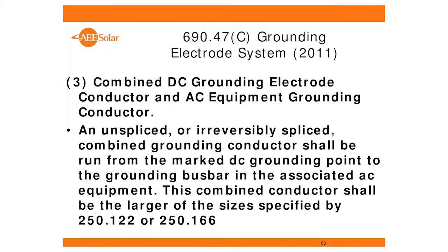Okay, so the common AC and DC grounding electrode is where I take our DC to ground here and our AC to ground there. The grounding electrodes go to the same location. And then we have something called a combined DC and AC electrode. And this kind of got some folks in the code a little upset with us. But we said, well, wait a minute. We've got an inverter, and we've got a terminal in the inverter, and we're going over to the main service panel, and we've already got to have an AC equipment grounding conductor in there for the AC circuit. And now you're telling us we've got to do a grounding electrode conductor from the DC side over to there. And they're both starting and stopping in the same location. They're both connected to the grounding electrode. So why don't we just take the larger of the two and call it good? And it basically is a combined one, it does both the AC equipment grounding conductor and the DC grounding electrode conductor. So that's what number 3 was.